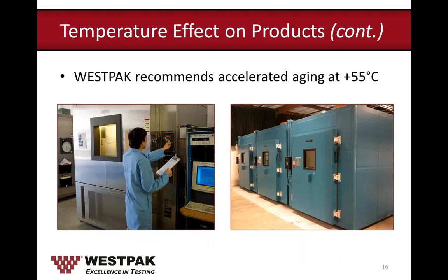WESTPAK is even more conservative and only recommends 55°C with uncontrolled RH. When we talk about aging, we are only controlling temperature — RH is uncontrolled. We have accelerated aging chambers at 50°C, 55°C, and 60°C readily available, and can typically start aging within one to three business days depending on the desired end date. Some customers prefer to delay the start so the study ends on a weekday when samples can be removed.